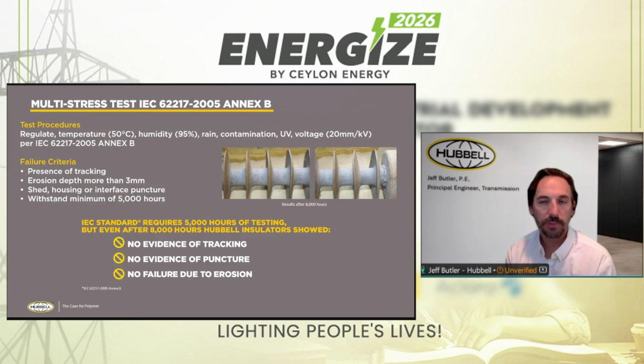So by almost simulating a small field environment, you're able to get a better understanding of the performance of the insulator as if it were out in the field. Similar failure criteria were evaluated for tracking and crazing, with an erosion depth of 3 millimeters. Unlike the previous test, where we did it on just plaques of rubber, this was done on actual sections of insulator, so you could evaluate the breakdown or degradation of the rubber that could expose the fiberglass rod. And then the threshold was set for us to a minimum of 5,000 hours.